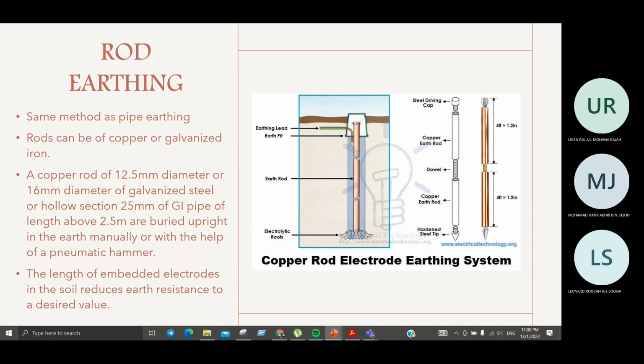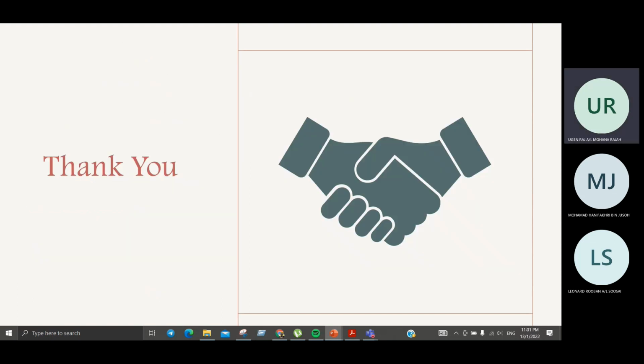As our conclusion, the method of grounding used by the electrician is wrong, because it does not comply with the regulation. Therefore, the electrician should have followed any of the 3 methods. But the most suitable method we can understand from these 3 is the rod method. This method is very suitable for this situation because this shop does not have any complex circuit and is built with a single phase circuit. Moreover, the rod method can be used in simple places like homes, offices, and restaurants. So from our conclusion, the method that can be used for this situation is the rod earthing system.